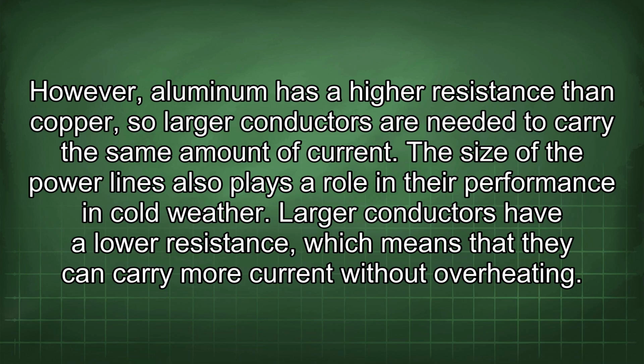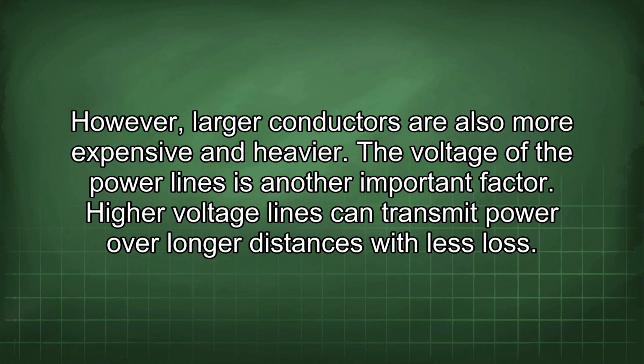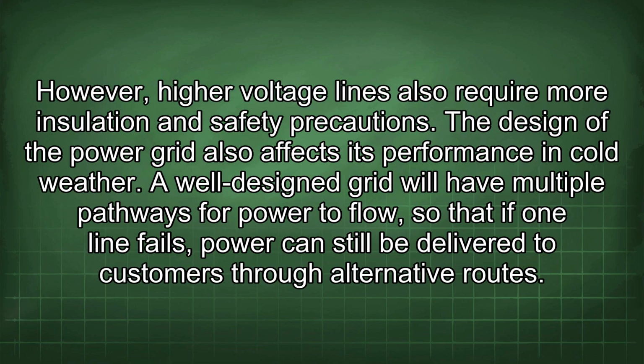The size of the power lines also plays a role in their performance in cold weather. Larger conductors have a lower resistance, which means that they can carry more current without overheating. However, larger conductors are also more expensive and heavier. The voltage of the power lines is another important factor. Higher voltage lines can transmit power over longer distances with less loss. However, higher voltage lines also require more insulation and safety precautions.